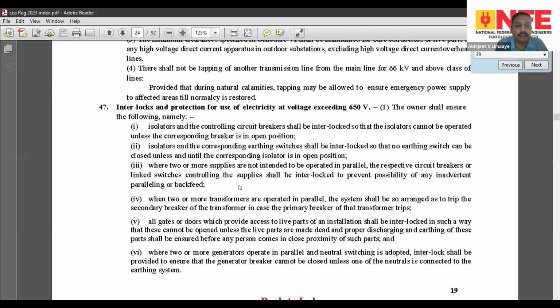Now, these days, we have provisions like automatic transfer switching. Here it is very important that it has to detect, and there has to be an interlock where the two supplies which are not supposed to be in parallel, the primary supply, should get disconnected before the secondary supply can be started. Now, I think subregulations 1 and 2 are predominantly related to medium voltage, where we have earth switches to discharge the cables. In that case, there is always an interlock between the breaker or the isolator and the earth switch, so that they cannot be switched on together.